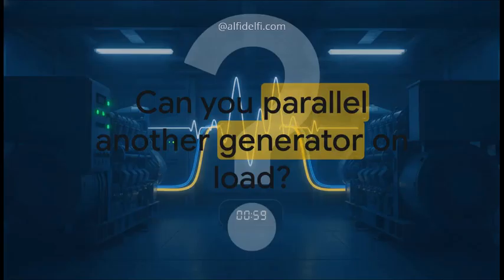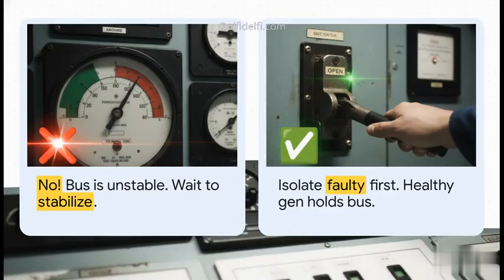And that brings us to a favorite question of surveyors to test your decision-making. During those crucial first 60 seconds of chaos, can you parallel or take another generator on load? Think really carefully about your answer here. For frequency fluctuation, absolutely not. No way. Immediate synchronization is practically impossible because the bus is wildly unstable. Your synchroscope will be spinning erratically. Attempting to close the breaker now risks an out-of-phase closure, massive circulating currents, or even a catastrophic explosion. You have to wait for the bus to calm down.